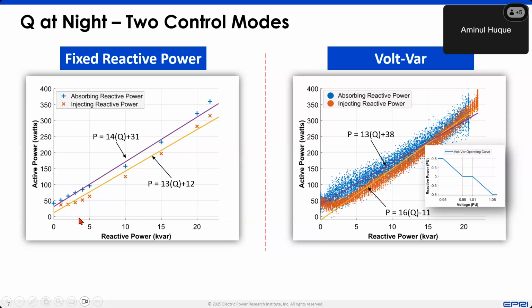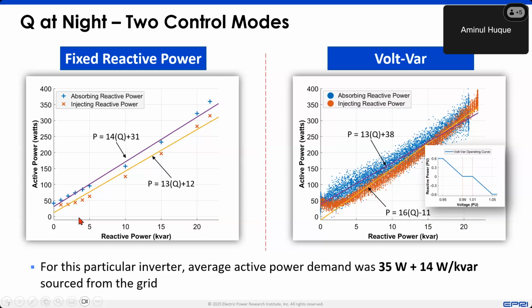And again, the high voltage inverter was absorbing VAR, and at low voltage it was injecting VAR, all the way up to 20 kVAR, or maybe a little bit higher than 20 kVAR. And for each of those reactive power values, what was the active power consumption from absorption by the inverter? That was captured. Again, these numbers vary a little bit, but in general, just to keep the inverter operating at 0 VAR, it takes around 35 watt just to stay on so that it can provide reactive power support. And then roughly, again, it's not an exact number, but for each kVAR, it was taking 14 watt.